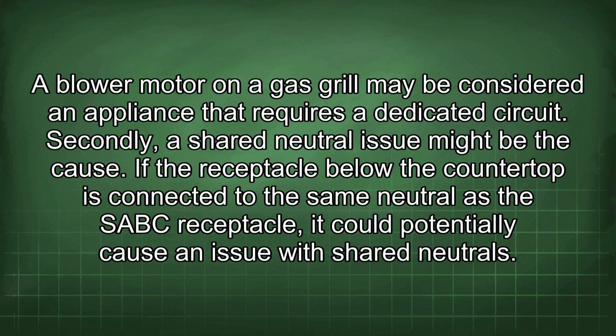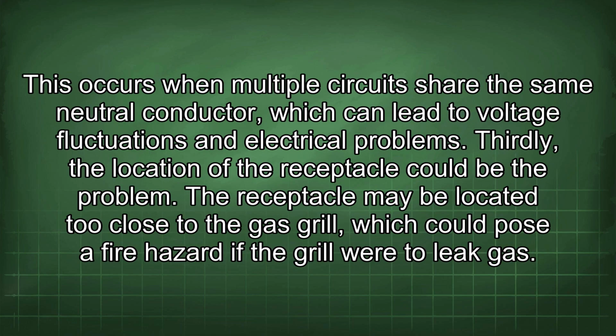Secondly, a shared neutral issue might be the cause. If the receptacle below the countertop is connected to the same neutral as the SABC receptacle, it could potentially cause an issue with shared neutrals. This occurs when multiple circuits share the same neutral conductor, which can lead to voltage fluctuations and electrical problems.